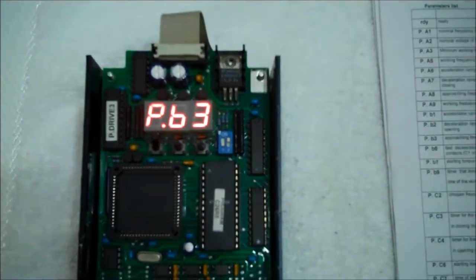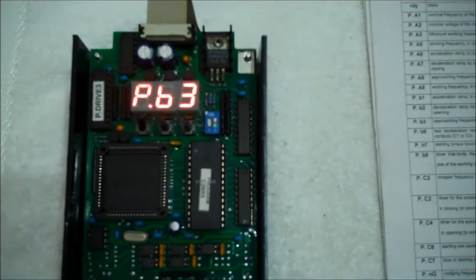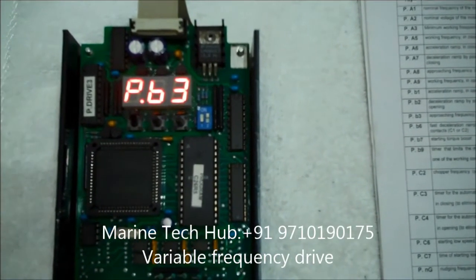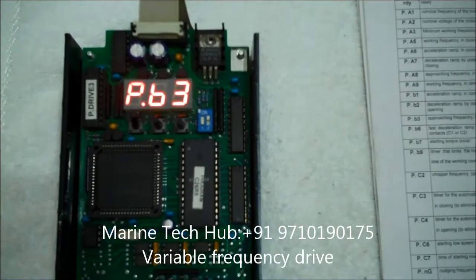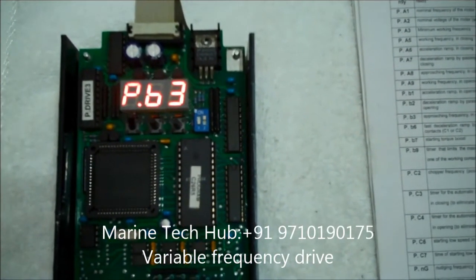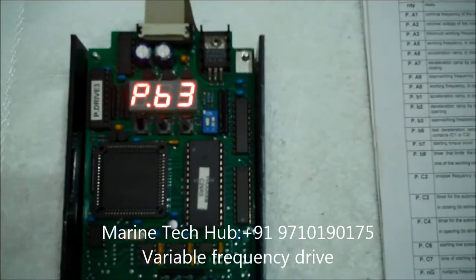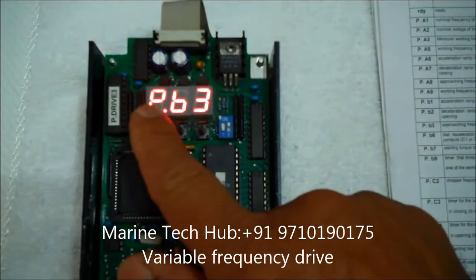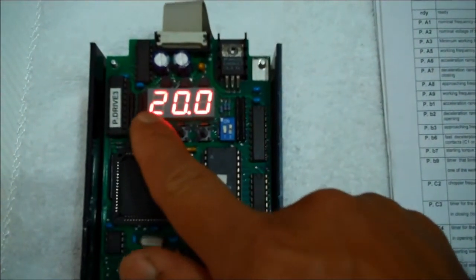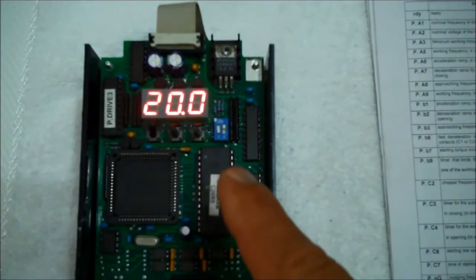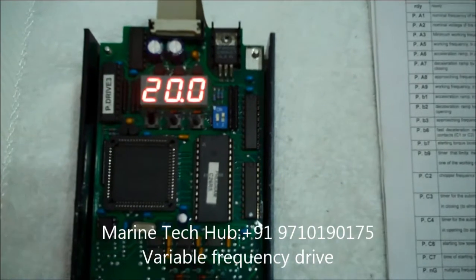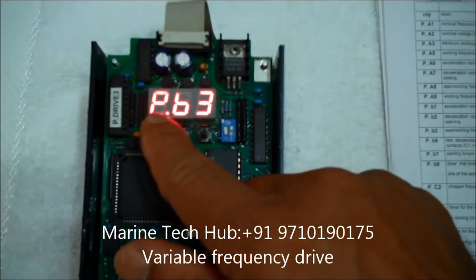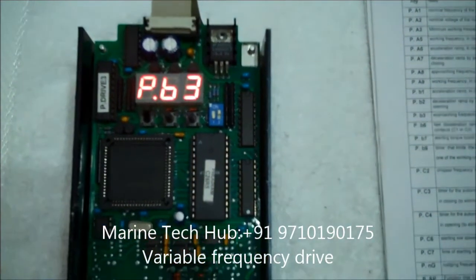Then next you can go to the next program. This is PB3. PB3 is the approaching frequency in opening. This is normally set at 20Hz. So if you press this you can see how much. It is 20Hz. I don't want to change it. I just want to show you how the programming is.